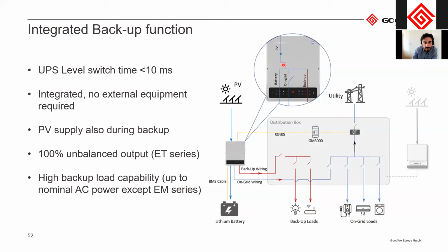It's possible to visualize it with this diagram. Here you see the PV energy coming in, the energy from the battery, here is the on-grid, and here's the backup output. When the grid is functioning as normal, this switch is closed. This means that both these loads and the backup loads are supplied from PV, from the battery, and from the grid, so there's no distinction in the division of the loads. But when the grid fails, this switch will open, disconnecting all the on-grid loads, and then the backup loads will be isolated from the grid and supplied only by the PV and the battery.